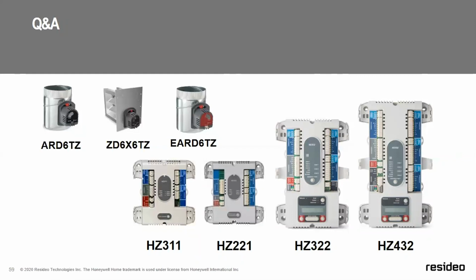And it wasn't until I came on board with Honeywell that I actually went out in the field and started discovering how important bypass is. And I hate to say this because I did really high-end work. I actually advised the people that took over my jobs to go back to these systems and install proper bypass. So yeah, bypass questions are great. And also bleed rate is very important, because a lot of those jobs that I did, if I had the actuators, I mean, I know I'm showing my age here, so these are going back before 2014. But if I had bleed rates or knew how to adjust the bleed rates, that would have helped, but bypass is certainly critical on a lot of those jobs.